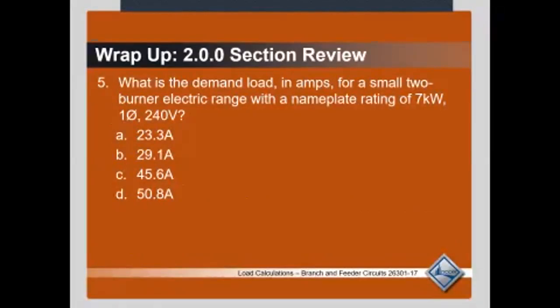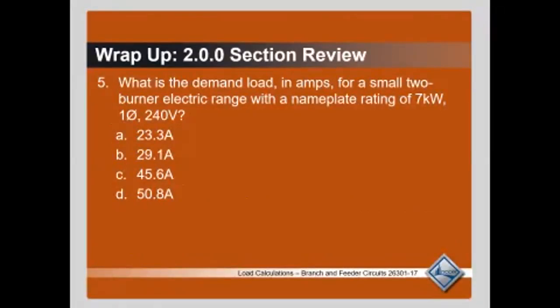What's the demand load in amps for a small two burner electric range with a nameplate rating of 7,000 volt amps, single phase, 240 volts? What is the load?